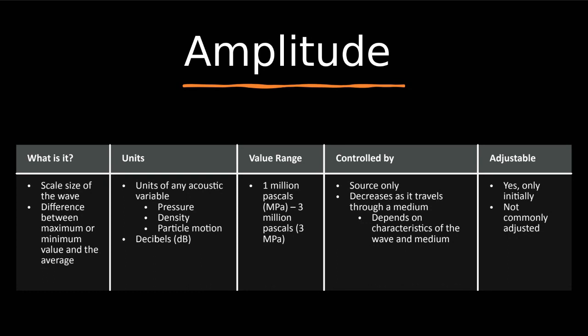We can adjust it initially, but it's not something that we commonly adjust. It is one of those in-depth user operator controls that there is the capability to adjust before you start scanning, but that's not something we are typically doing in our day-to-day job. So it's mainly controlled by the ultrasound source when we're selecting our exams and our transducers.